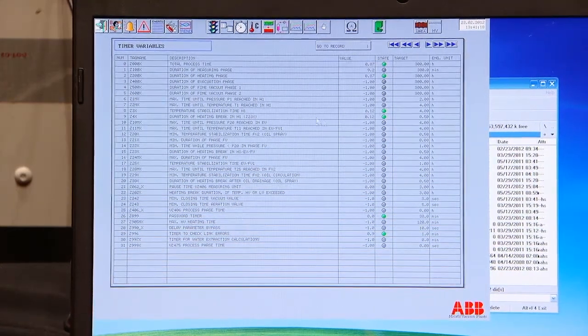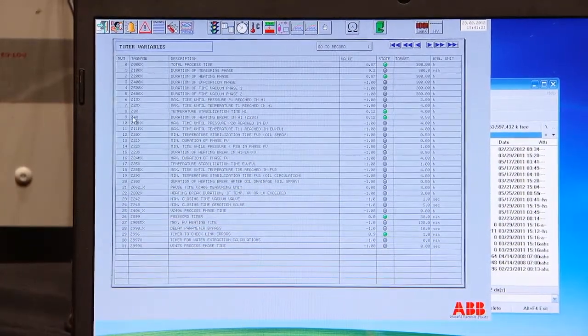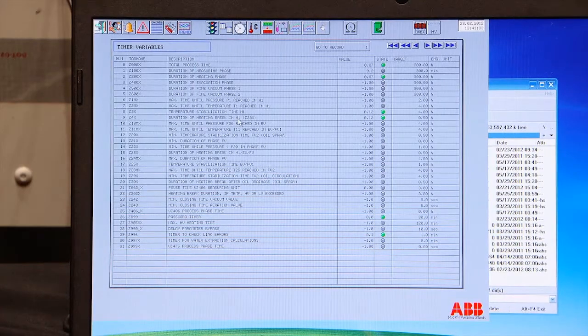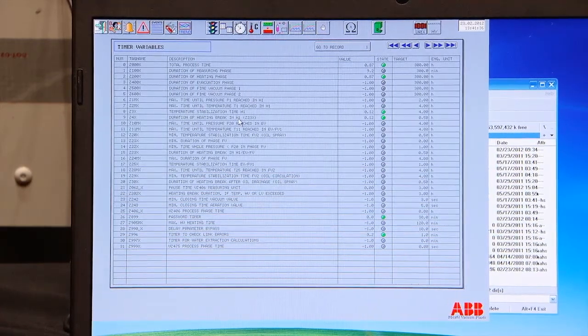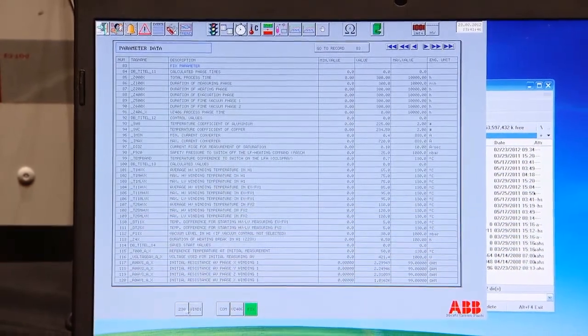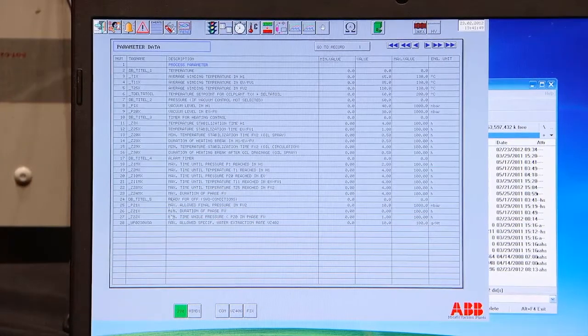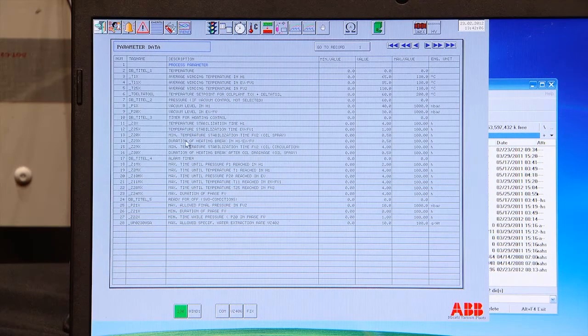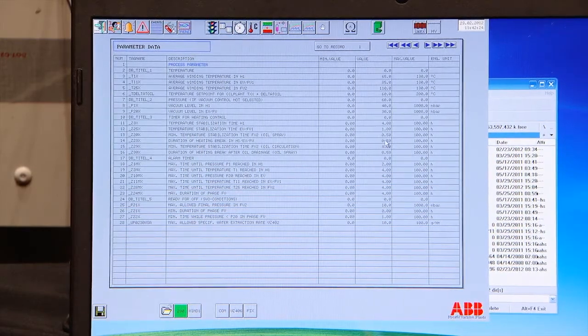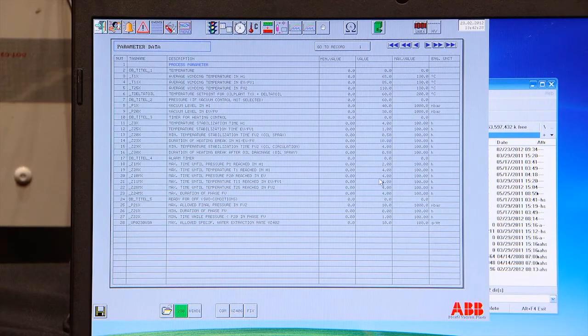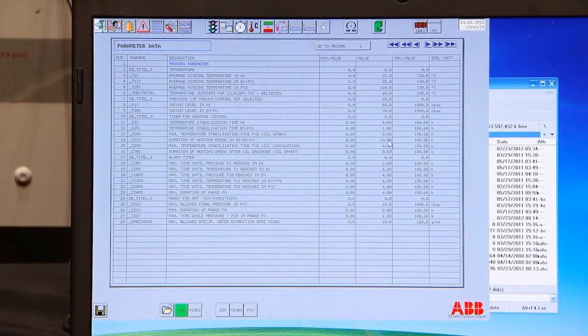This is now the timer called Z4X, duration of heating break. You want to make that longer now. There are two things: temperature stabilization time and heating break. The heating break we have under the process page. Here's the duration of heating break, row 14. Take a value of 10 hours. That should be enough. Then the plant will not start until we are back.